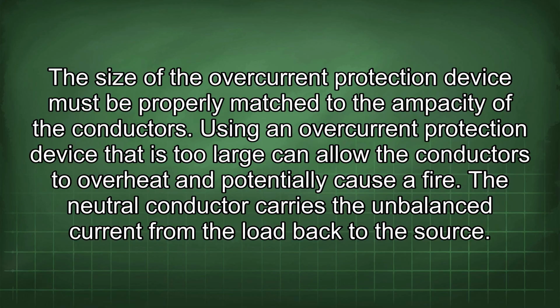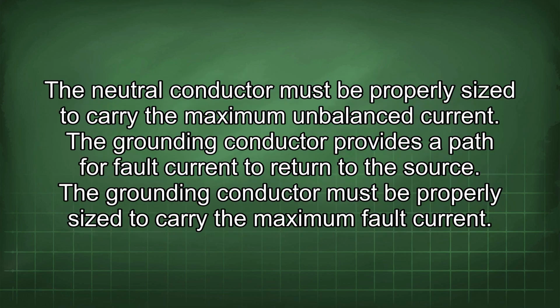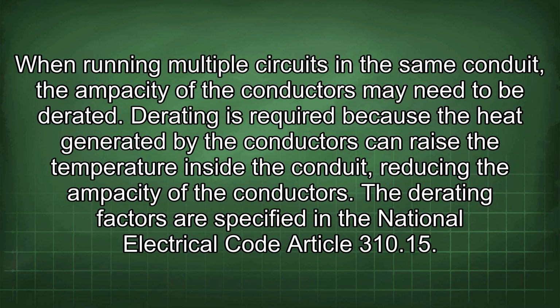The neutral conductor carries the unbalanced current from the load back to the source. The neutral conductor must be properly sized to carry the maximum unbalanced current. The grounding conductor provides a path for fault current to return to the source. The grounding conductor must be properly sized to carry the maximum fault current. When running multiple circuits in the same conduit, the ampacity of the conductors may need to be derated. Derating is required because the heat generated by the conductors can raise the temperature inside the conduit, reducing the ampacity of the conductors. The derating factors are specified in the National Electrical Code Article 310.15.